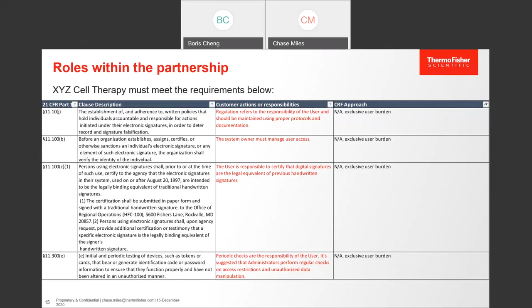Here's an example of where both XYZ and the Cryomed manufacturer must meet a requirement within 21 CFR Part 11. When it comes to the ability to generate accurate and complete copies of records in both human readable and electronic form, suitable for inspection, review, and copying, there is a burden on XYZ and there is a burden on Thermo Scientific as the manufacturer of the Cryomed. So you see, this idea of a partnership is really coming to fruition in that there are clear rules and responsibilities a customer must meet, just as there are clear rules and responsibilities the manufacturer needs to meet.